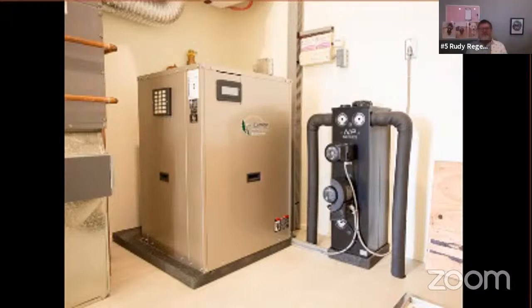So, first of all, this is a very unusual system that you are taking your heat source from the pond. That's actually quite unusual, is it not? Well, not really. It's just in most homes, they don't have the option to have a pond. But anytime we come to the farmers or acreage where a dugout or a pond is available that's more than 12 feet, we will actually encourage them to do a pond loop. I've probably done about a dozen pond loops. Okay. It's not as common, obviously, but it definitely works.